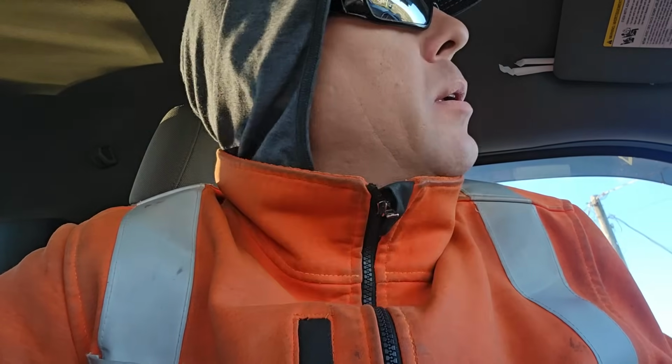Okay, perfect. So 2 out of the 3 phases are open at 8209 SO10. Yeah, copy that. 2 out of the 3 phases are open. 8209 SO10. That's correct. We have a tree across the 3-phase at pole T113. T113. You got a tree on the 3-phase. 10-4. And it looks like I can use a normal open here, 8209 SO46. 8209 SO46, a normal open.